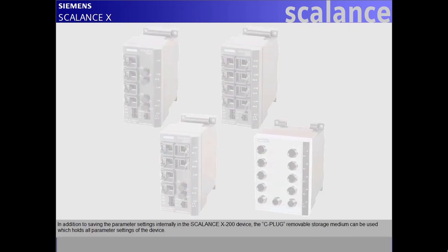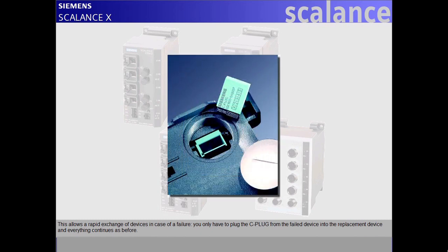In addition to saving the parameter settings internally in the Scalance X200 device, the C-Plug removable storage medium can be used, which holds all parameter settings of the device. This allows a rapid exchange of devices in case of a failure. You only have to plug the C-Plug from the failed device into the replacement device and everything continues as before.